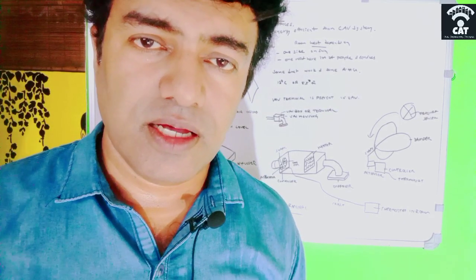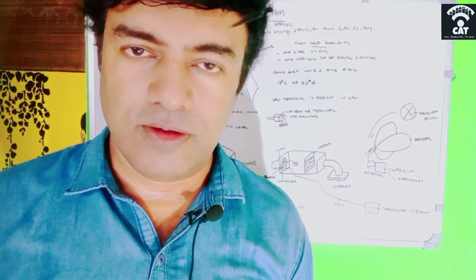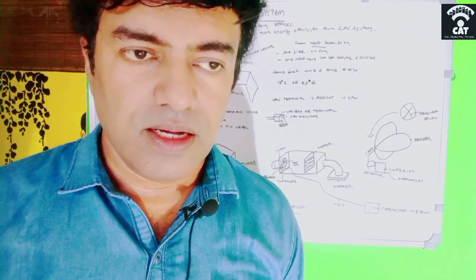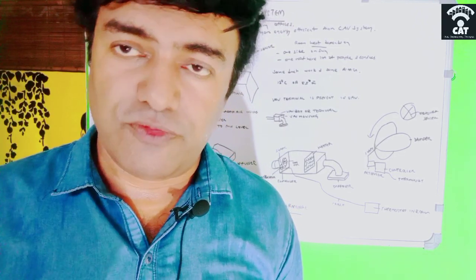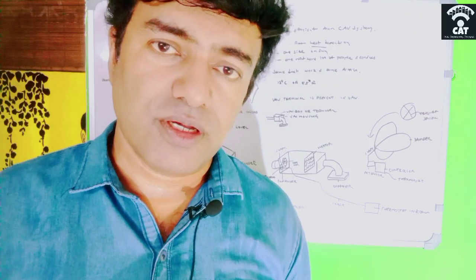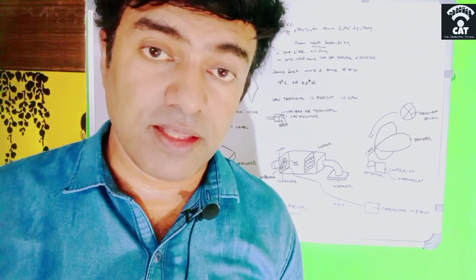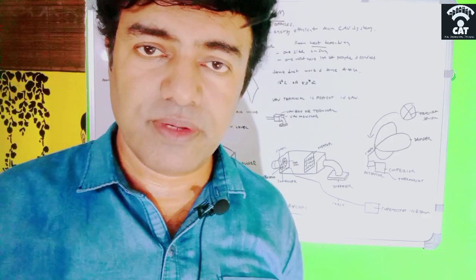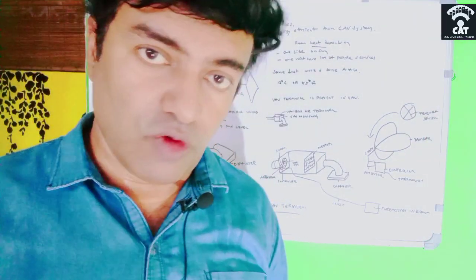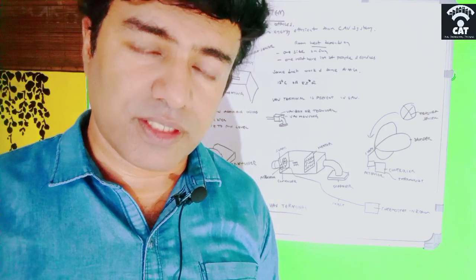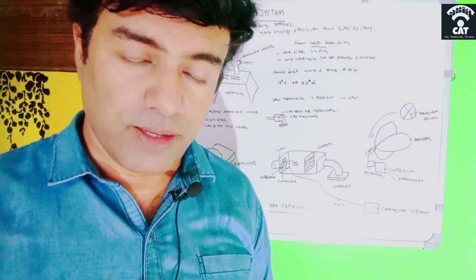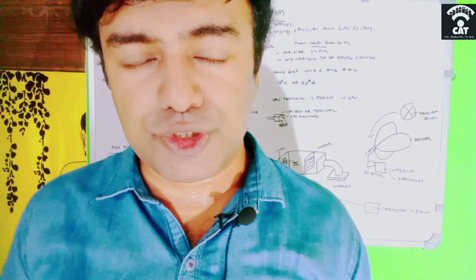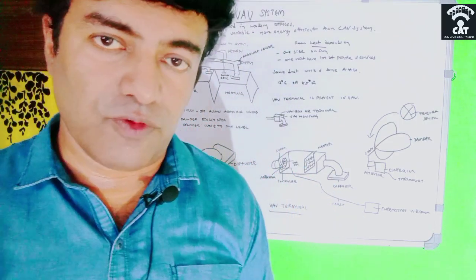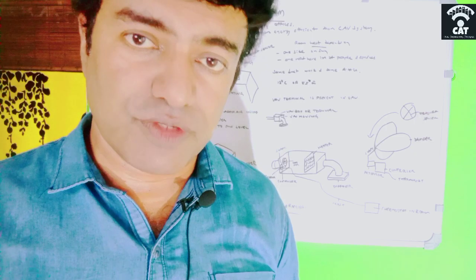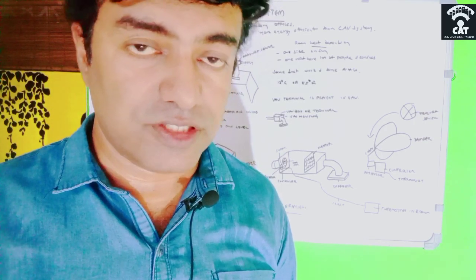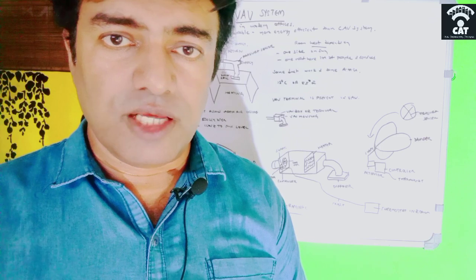Today's subject is VAV system, or Variable Air Volume System. This is a particular type of ventilation system in which the volume of air will be different, maintaining a constant temperature of the air. It is being used for ventilation in modern offices. Previously we used the constant air volume, that is CAV system. Now it has changed to VAV system, variable air volume system, because this is more energy efficient than the previous CAV system. So let us go deep into this.